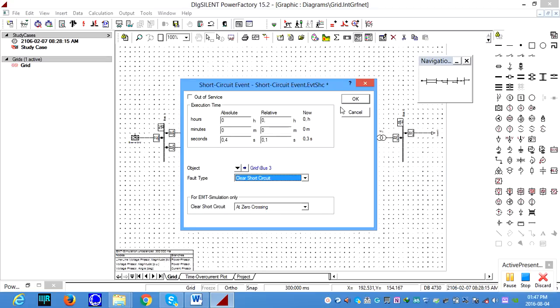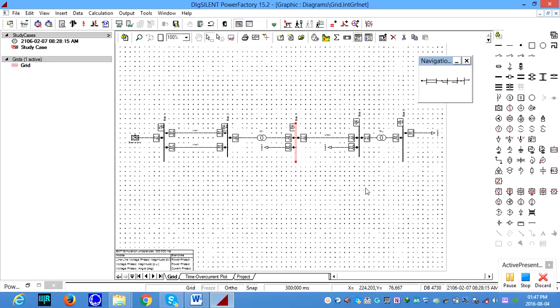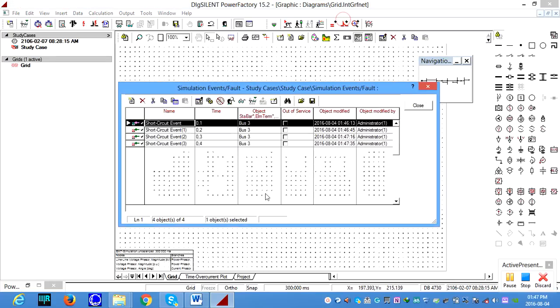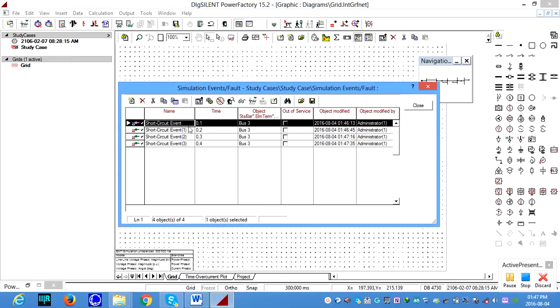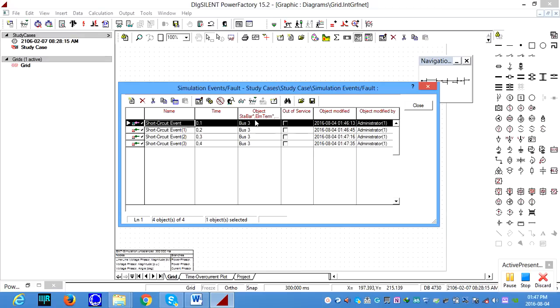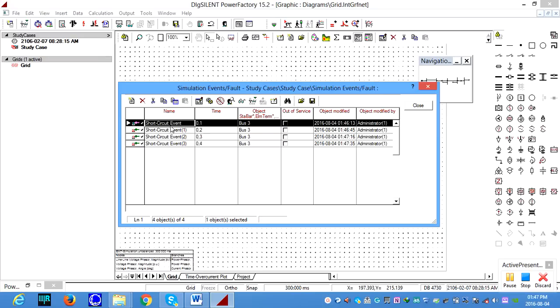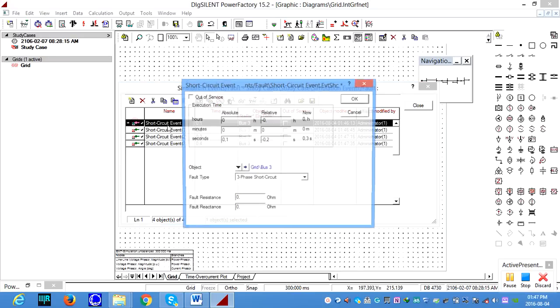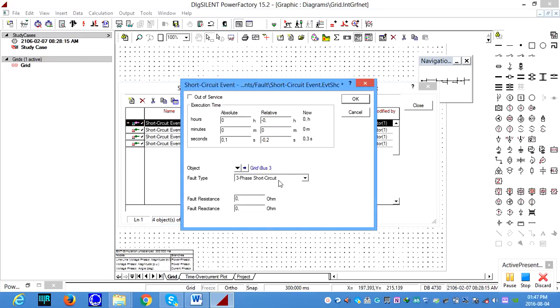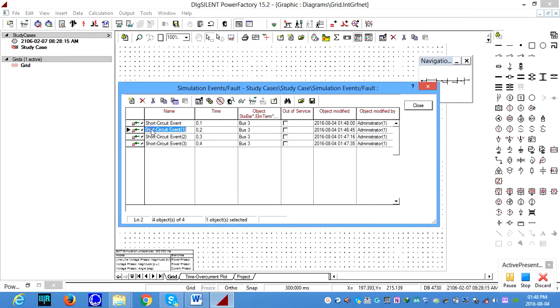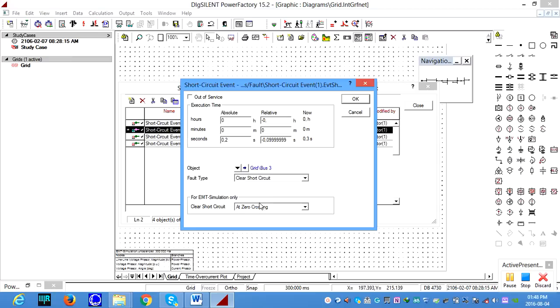0.4 seconds we are clearing. Okay, in order to see all the events that you applied, you click here. You see here, at 0.1 there is a short circuit introduced, at 0.2 seconds there is a short circuit cleared, at 0.3 seconds, if you want, you can click here. Okay, if you go and rename it accordingly, this is a three phase short circuit, we rename it. So it's introduced at 0.1. If you click here, the three phase short circuit, you see this is cleared at 0.2 seconds.